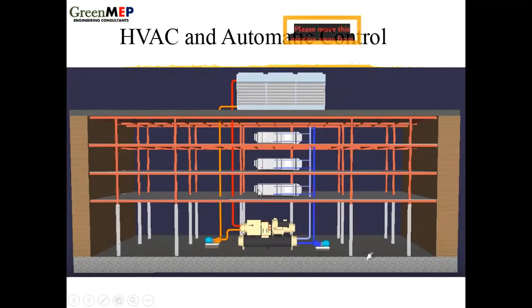Okay. So the thing is, if there are lots of people in this space, there is lots of heat to remove. When there's a lot of heat to remove, this water will flow very fast. The flow rate, cubic meters per minute, will be higher. If the amount of heat to be removed is high, we say the heat load, the thermal load, is high, right? And then these pumps will work fast. The compressor here, the chiller, will have to work fast, right? More refrigeration cycles per minute. They have to work fast because a lot of heat has to be removed here. So this water has to run faster, and these pumps will work fast. That means here there's a cooling job to be done, to cool down the condenser water. The fans in here will have to work faster. So you can see there's more heat to be removed, more work for the fans, pumps, and compressors.